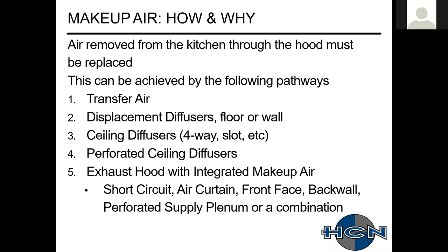And then typically for most designs with hood systems now, you're going to have an integrated makeup air source from the hood manufacturer themselves. First off the bat was short circuits, or recirculating hoods, as some people would call them, then air curtains, front face or front discharge, your back wall or back return, and then for the most part, most manufacturers have settled on a perforated supply plenum, a makeup air plenum box up in the front of the hood. Some manufacturers will do a combination, which is typically probably your best bet.